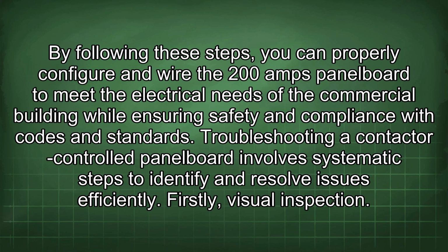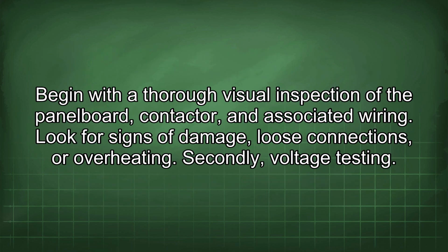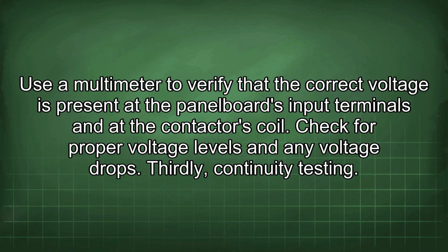Troubleshooting a contactor-controlled panelboard involves systematic steps to identify and resolve issues efficiently. Firstly, visual inspection. Begin with a thorough visual inspection of the panelboard, contactor, and associated wiring. Look for signs of damage, loose connections, or overheating. Secondly, voltage testing. Use a multimeter to verify that the correct voltage is present at the panelboard's input terminals and at the contactor's coil. Check for proper voltage levels and any voltage drops.